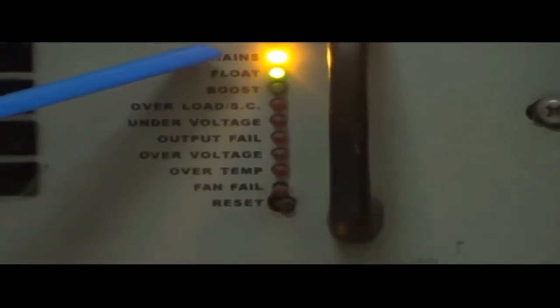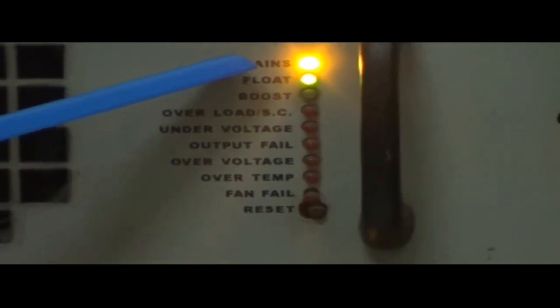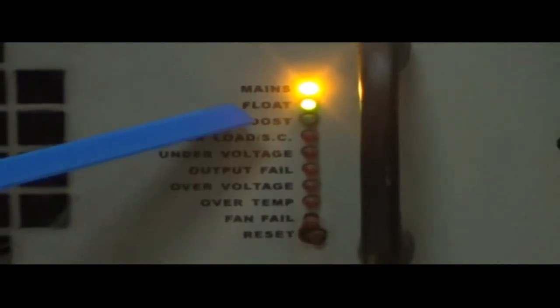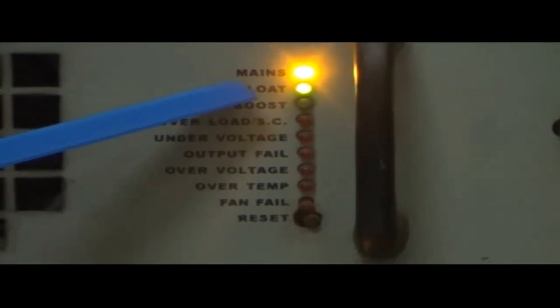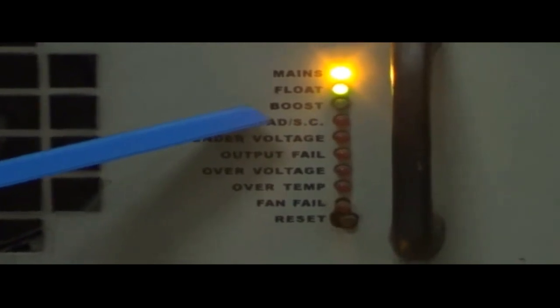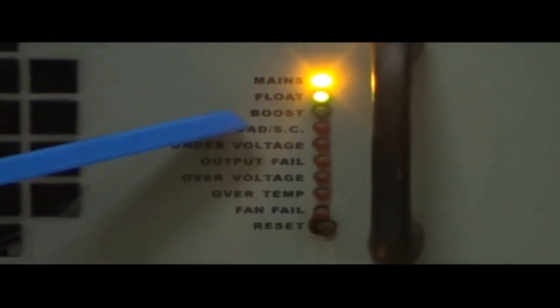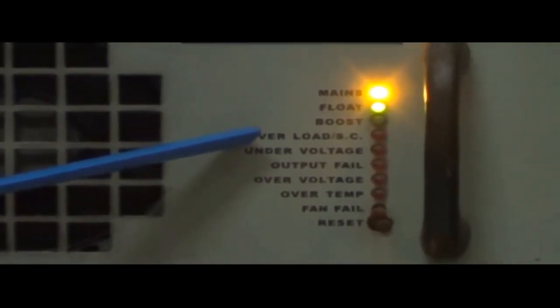Mains: It indicates that main supply of the module is on. Float: This indication shows that the module is in float or charging. Boost: This indication shows that the module is in boost mode of charge. Overload or short circuit: This shows that the module is overloaded. There is more than 60 volts.